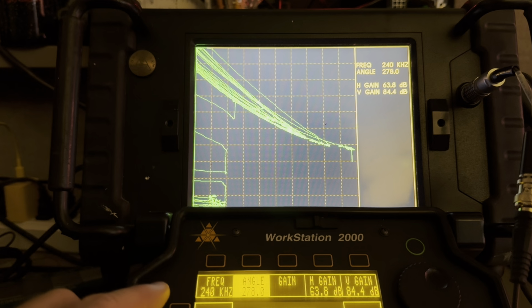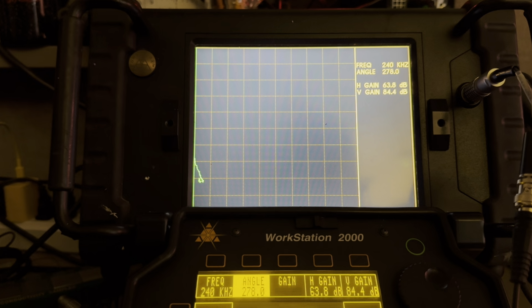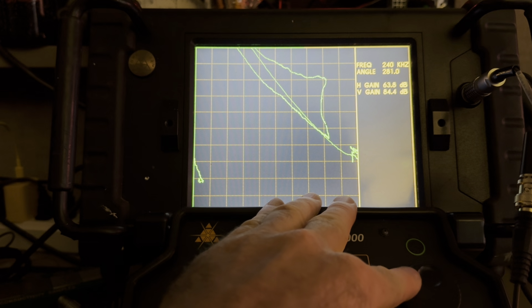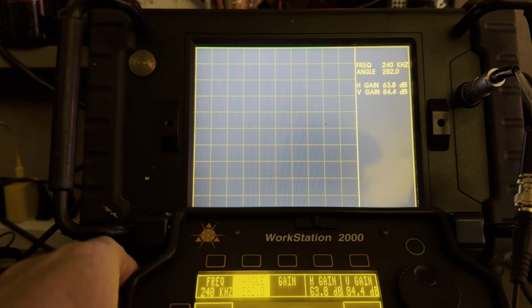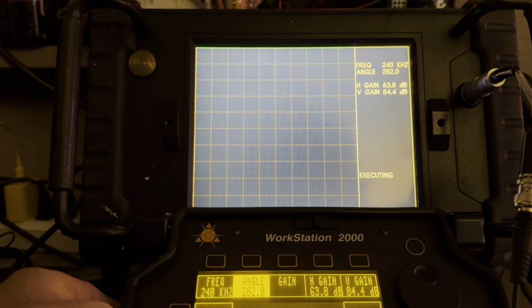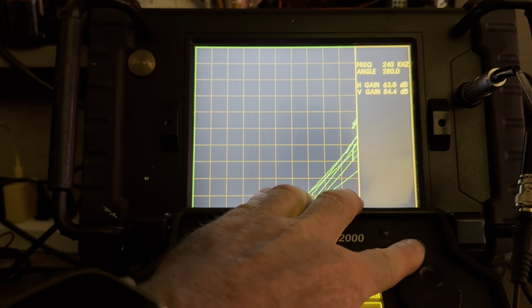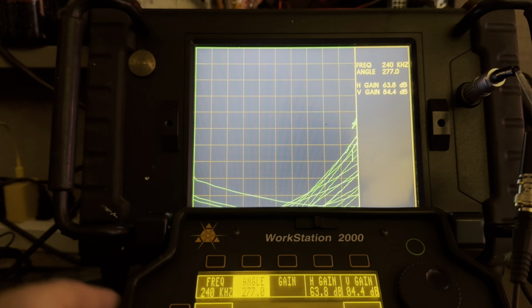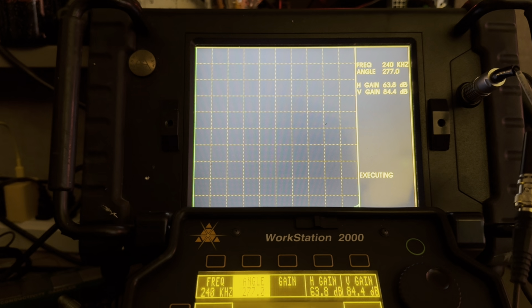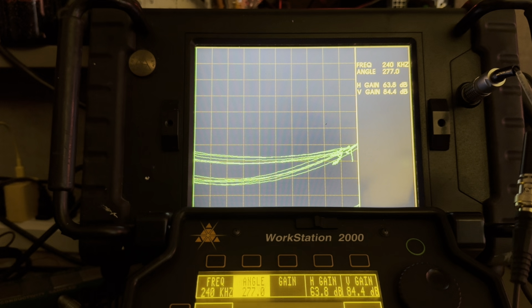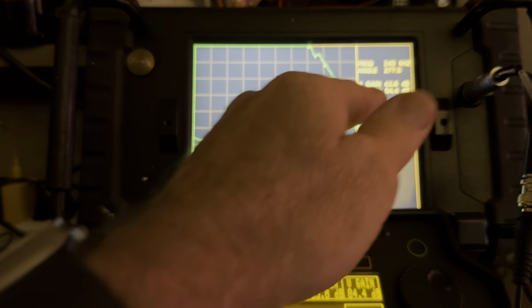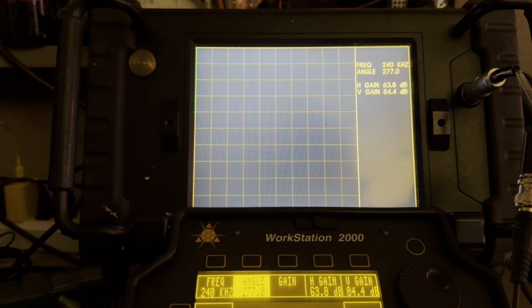Now, because I have substantially more vertical gain than horizontal gain, when I go to adjust the smart knob to adjust my rotation, you don't have to move it much. You don't have to move it much at all. You do have to null, though, if you want to keep your signal on the screen. Just a couple clicks will bring it flat. Okay, let's see if we're in the ballpark. Yeah, so when you adjust the vertical gain more than the horizontal gain, what it's going to do is skew your signal a little bit, and it's going to give a curvature to the liftoff line. But that's okay, just as long as you're aware that that's what's happening. Let me hit null. Null's your friend.